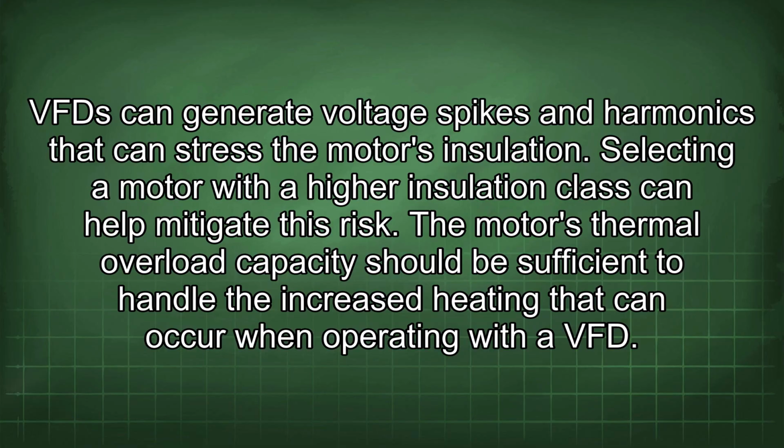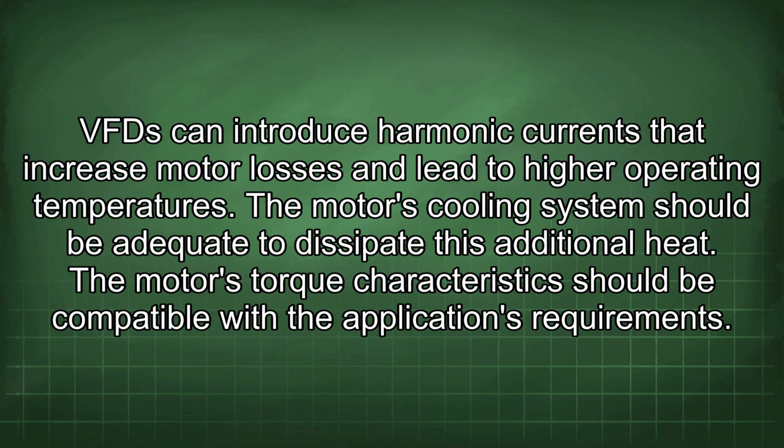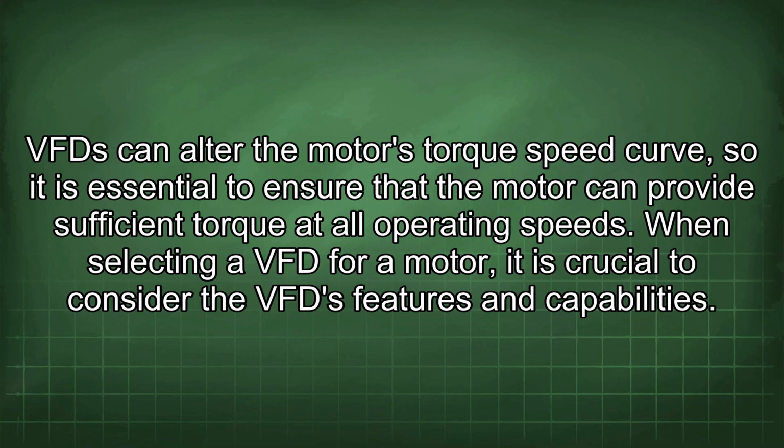The motor's thermal overload capacity should be sufficient to handle the increased heating that can occur when operating with a VFD. VFDs can introduce harmonic currents that increase motor losses and lead to higher operating temperatures. The motor's cooling system should be adequate to dissipate this additional heat. The motor's torque characteristics should be compatible with the application's requirements. VFDs can alter the motor's torque speed curve, so it is essential to ensure that the motor can provide sufficient torque at all operating speeds.